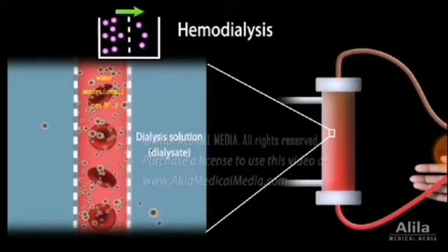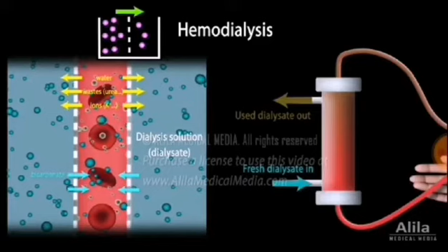Inside the machine, blood flows in tiny tubes surrounded by dialysis fluid called dialysate. The walls of the tube act as a semi-permeable membrane, allowing only small molecules such as water, nitrogenous waste and electrolytes through osmosis and diffusion. Dialysis fluid contains solutes at a level similar to that of healthy blood. Urea, potassium and other solutes present at higher levels in the patient's blood move out of the blood into the dialysis fluid through diffusion. The dialysis fluid is constantly replaced and discarded, and at the same time fresh dialysate is continuously added.